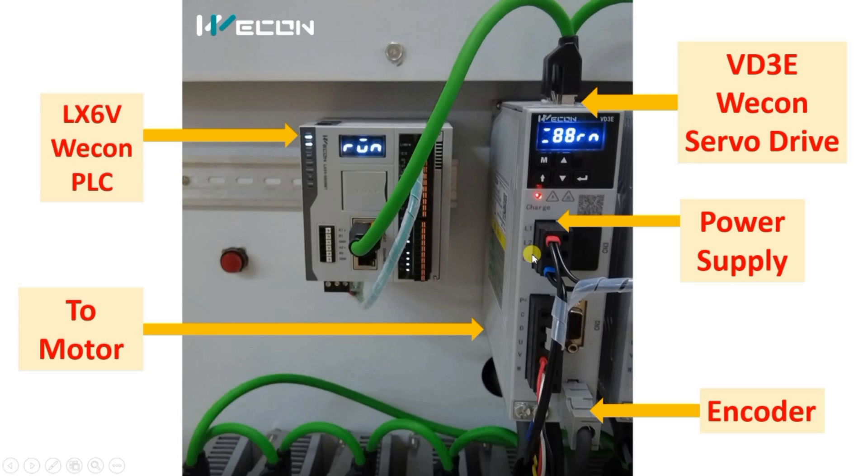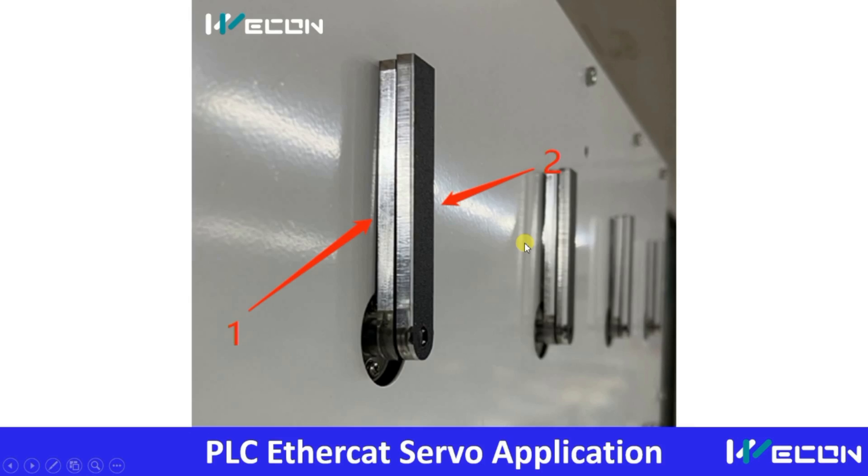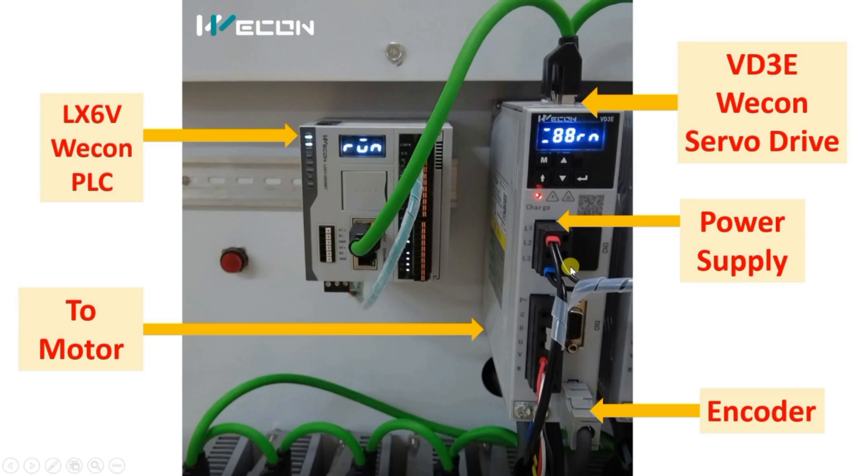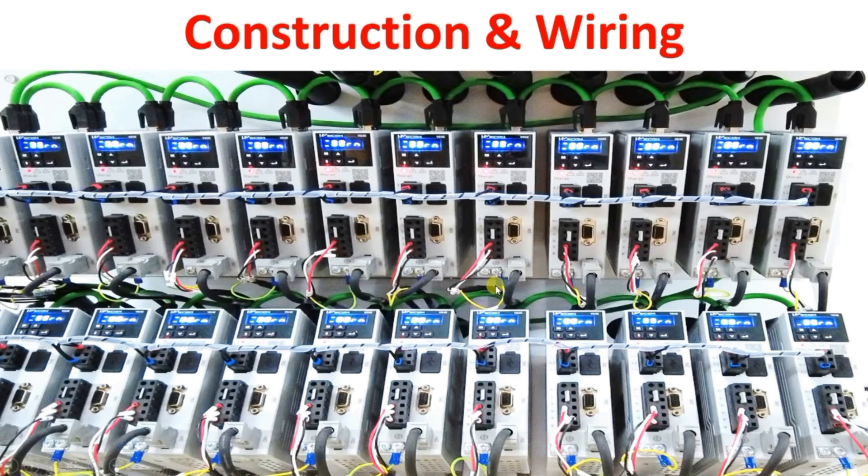Now we will understand the wiring of the servo drive. Here you can see L1, L2, and L3 — this is the main input supply. It is single phase, and the main input supply is linked to each servo drive: common power comes in and is looped to each and every drive. Here you can see U, V, W — this is given to the servo motors. This is the encoder cable coming from the servo motor, connected here, and the Ethernet cable is connected as well. This is the Wecon VD3E model servo drive.